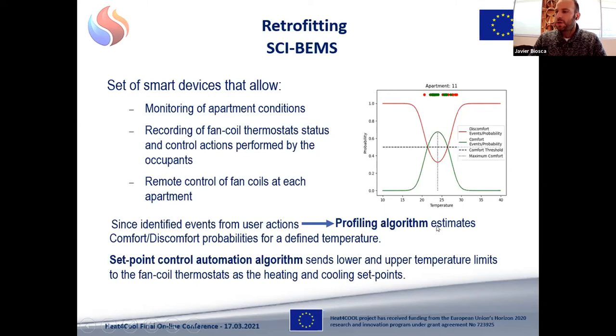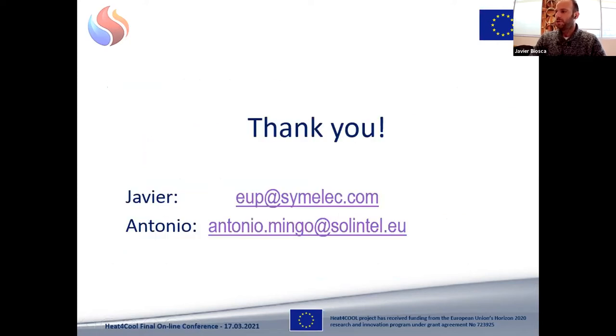And then the set point control automation algorithm of the SCI BEMS sends the lower and upper temperature limits to the fan coil thermostats as the heating and cooling set points. And this is all about the retrofitting we have done in the Valencia pilot site.